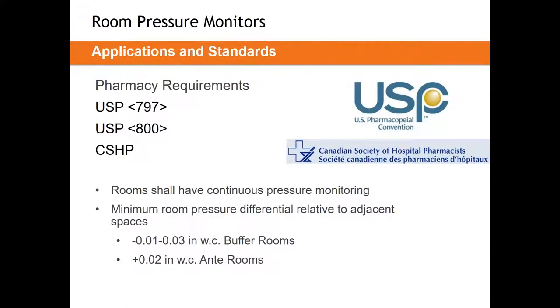Most of the information on compounding pharmacies comes from USP 795, USP 797, and USP 800. There is some information in ASHRAE 170, but it typically refers back to the USP standards for pressures and air change rates. Both USP 797 and USP 800 require continuous pressure monitoring — just like the isolation room, we must have room pressure monitors in compounding pharmacies. They are an absolute must.